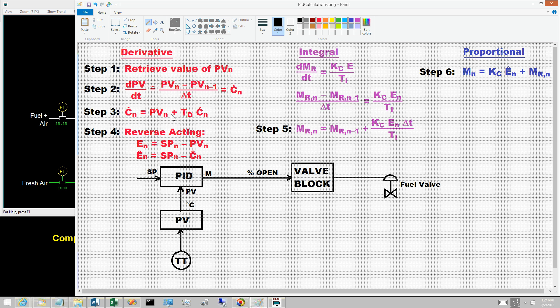Step three computes the projected value C-hat sub n as the current value of the PV, PV sub n, plus T sub d times the rate of change C-dot sub n. Step four computes the control error and the projected control error E-hat. This depends on the action of the controller. For reverse acting: E sub n is set point sub n minus PV sub n, and E-hat sub n is set point sub n minus C-hat sub n. For derivative based on E, steps two through four are similar.